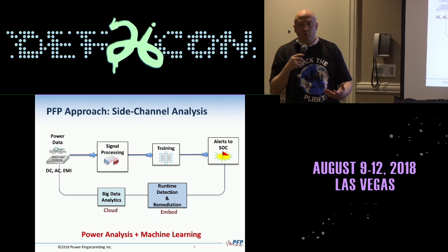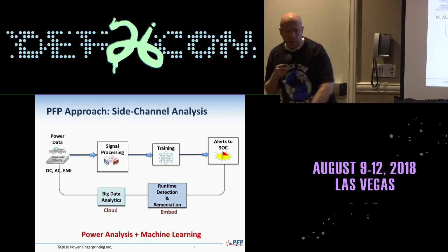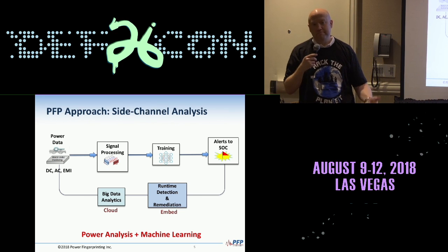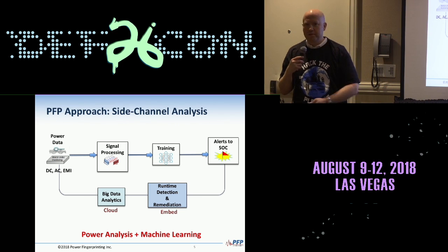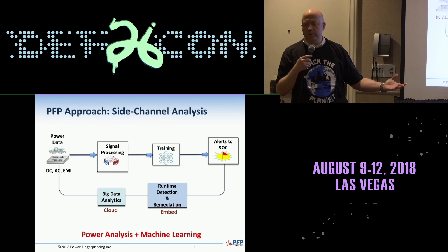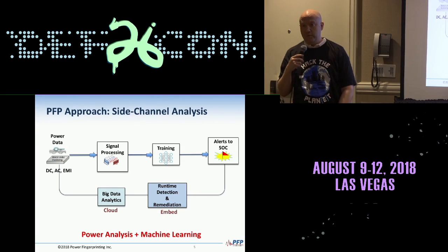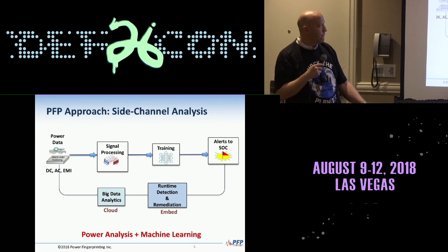I had another company that, as far as I could tell, was truly air gapped. They had completely severed any IP connection into the system. Cool. How do you update the firmware? Oh, we go over to the internet machine, download the firmware, put it on a thumb drive, walk over to the machine and load it. Okay, technically an air gap, but obviously another vector. And since they had no other software or device to protect the system because, hey, we're air gapped, what could possibly go wrong? They were doing that, which post-Stuxnet, everybody knows, doesn't work.